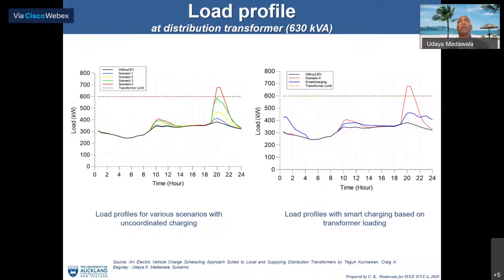So what can we do? We came up with a way of doing this: with a controller that looks at the transformer loading, we can distribute the charging pattern to mitigate this issue. On the right-hand side, the blue curve shows we can bring demand down well below the limit, while still charging the same number of vehicles through energy shifting—within the capabilities of the transformer. Many people have done similar approaches. What I'm trying to explain is that this is another way of mitigating the problems associated with the impact on the distribution network, as well as the power network.